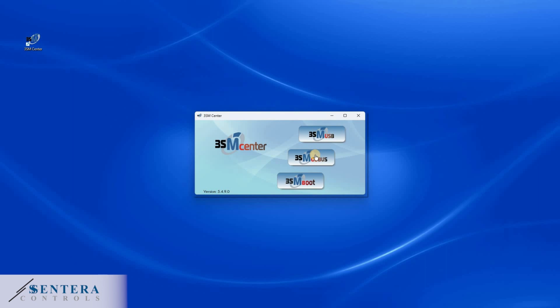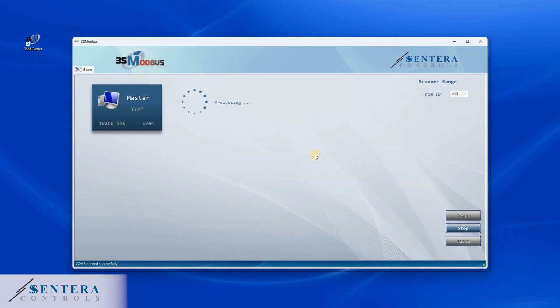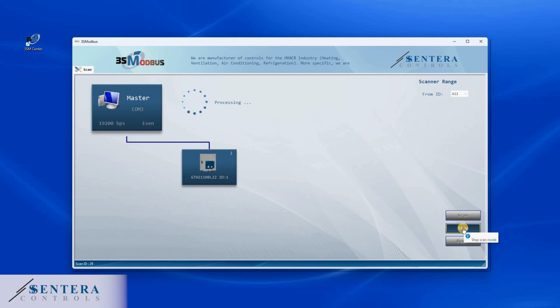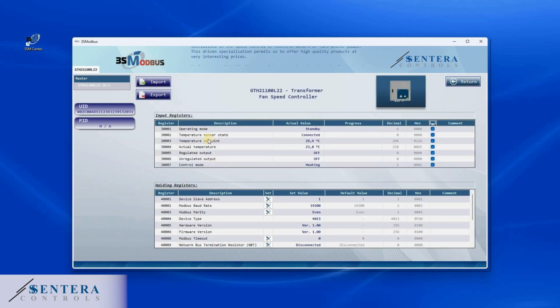I'm going to show you what you will see on your computer. From 3SM Center, click on 3SModbus. It recognizes the controller automatically. Click on the controller to select it. A new window with the Modbus registers of the device opens.